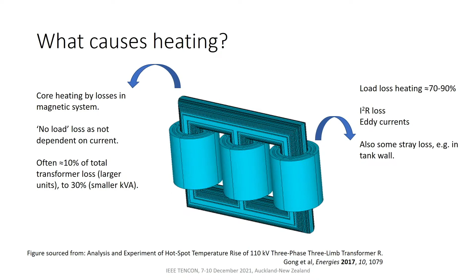When we look at the load loss heating, that can be anywhere between 70 and 90%, again depending on the capacity of the transformer. In that load loss we have our I²R losses and our eddy currents. We also have a certain component due to stray losses, such as in the tank wall. If there are any magnetic components, they tend to produce higher stray losses than non-magnetic steel.